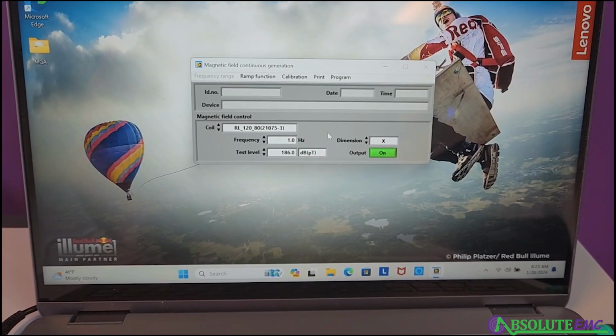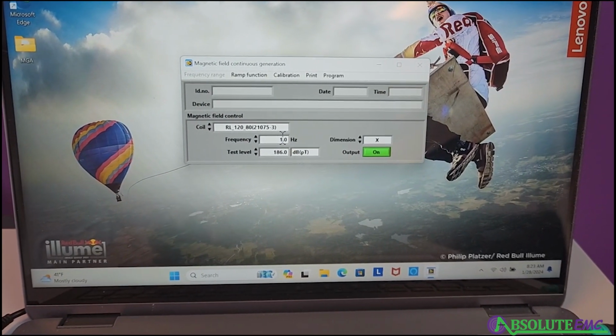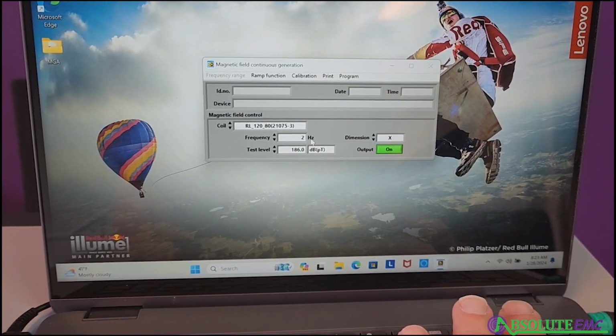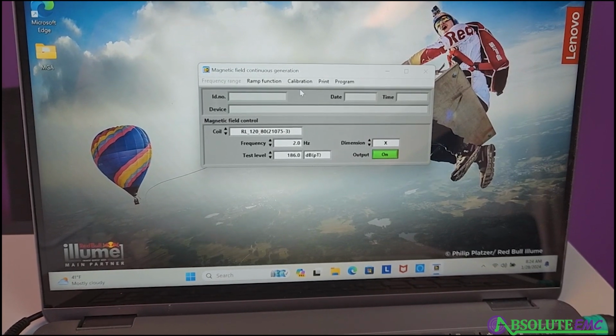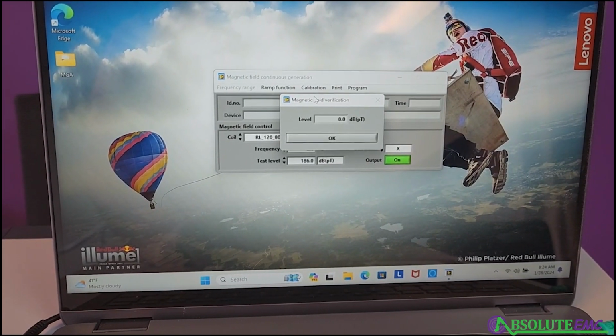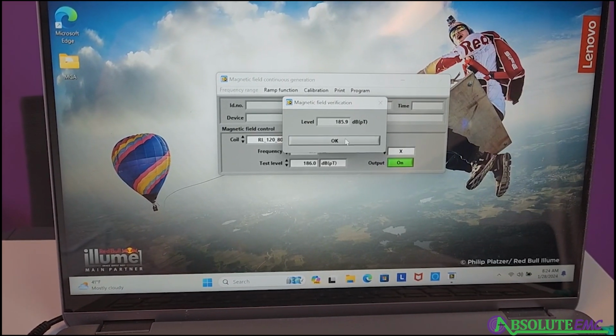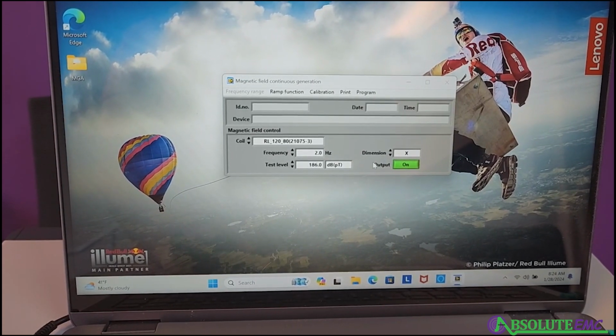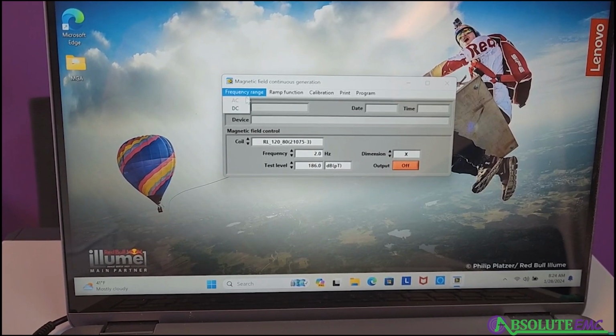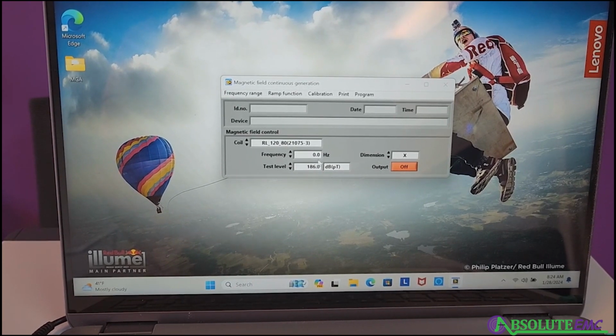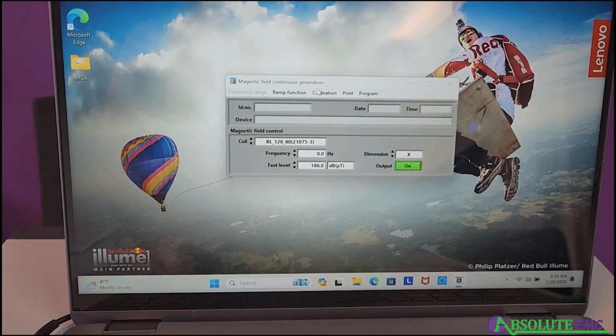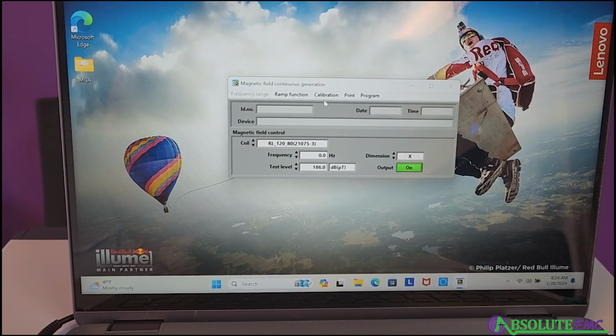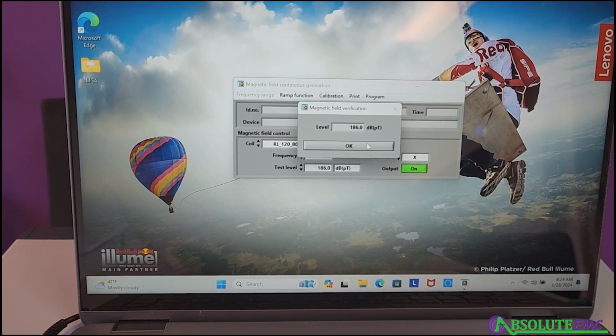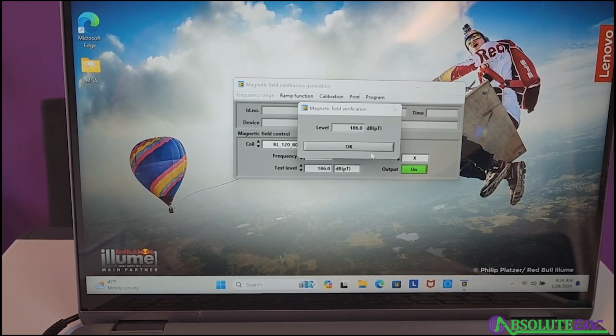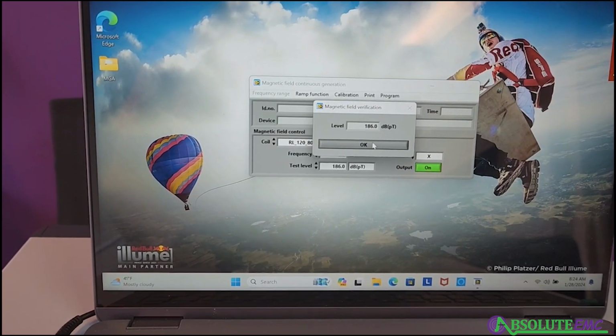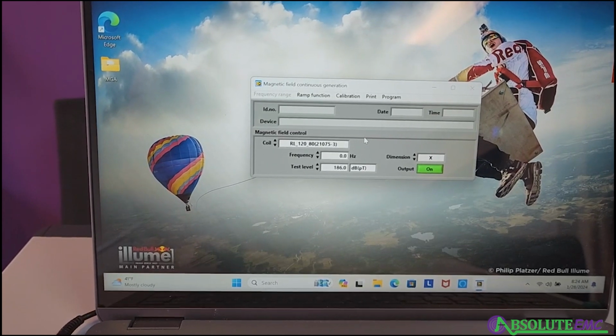And now we can take that Hall sensor off and do the test on our product for 1 hertz. And we can just change the frequency to 2 hertz. Current regulation. We want to verify that again. There we go. Now to do a DC test, turn this off. And we'll go here and switch our testing to DC. And there, so we're at 0 hertz. And basically have the same setup. Turn that on. Field verification. And we're at 186 dB picoteslas. And then we can do our testing at DC.